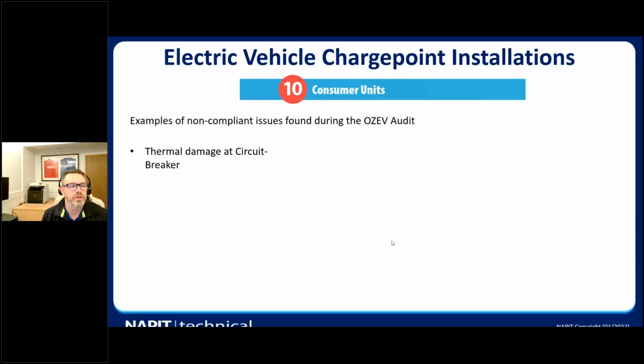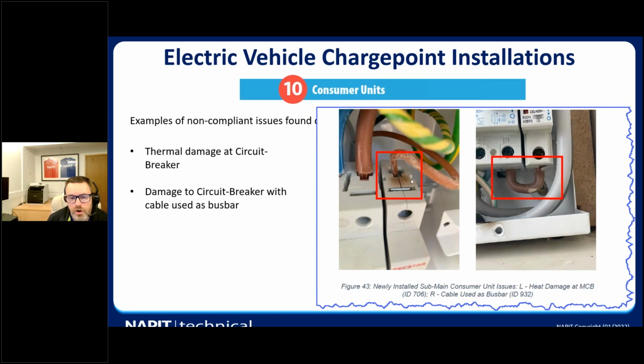Other examples of the consumer unit issues were thermal damage at the circuit breaker, and damage to the circuit breaker, which was used with the cable as a busbar. You see here the browning of the circuit breaker, which was either from a loose connection or a poorly terminated connection. On the side here, a bit of cable has been used to extend the charge point, and you can see the cables sticking out the bottom of the breaker, and there's damage to the breaker as well here.